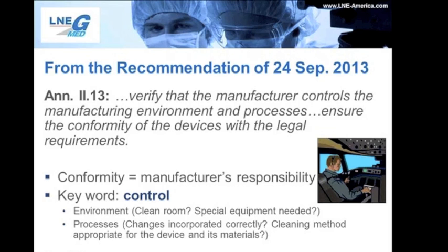Now, you'll always hear of horror stories where a manufacturer contracts out manufacturing of a high-risk device. It needs to be manufactured in a clean room and with very tight controls and all of that. And everything goes fine with all the paperwork and the communication until the manufacturer decides to do an audit and pulls up to the address of the factory, and it's actually a totally open-air factory with things like mold and rodents and stray animals and stray cats and screaming children and mosquitoes and bugs and flowers and dirt all over the factory floor with no mechanical ventilation in sight. So in other words, not a clean room or any definition of either of those in any situation.